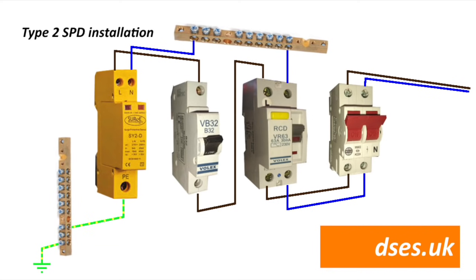That breaker can be one dedicated to the task, or if space is sparse, perhaps use one that also serves another circuit. Obviously neutral connects to the neutral bar associated with any RCD the breaker is hanging off. It's earth leakage free, so shouldn't trouble any RCDs located upstream, at least not in the case of this particular Type 2 model, although Type 1 SPDs are a different kettle of fish according to the Blue On-Site Guide. Regulation 534.4.7 requires any upstream RCD to have immunity to surge currents of at least 3 kA, but devices compliant with BS EN 61008 and 61009 do satisfy this requirement. Effectively, this SPD is treated as a final circuit in its own right.